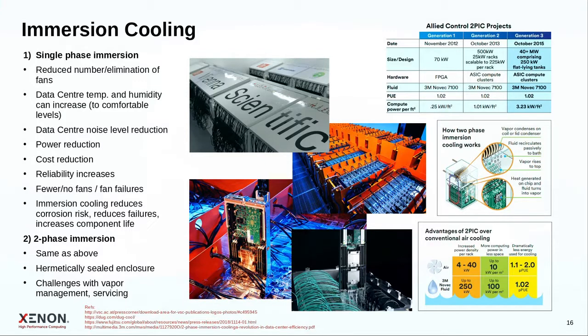Really the advantage of what we call single phase immersion, because you're just using the liquid phase. The advantages are you can essentially reduce or completely eliminate fans, because to get the systems in, you have to remove all the fans and essentially all the heat sinks, and then update your BIOS to make sure the BMCs and BIOS don't go crazy when there's suddenly no fans and they think they're not cooled properly.